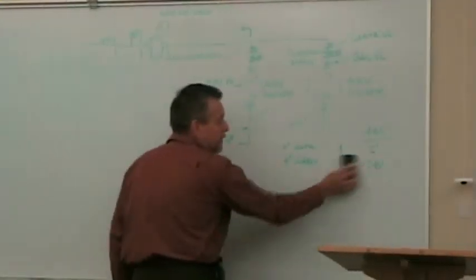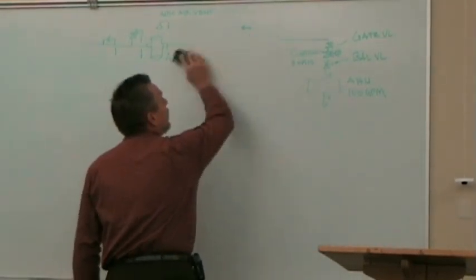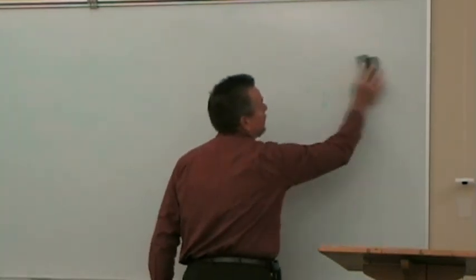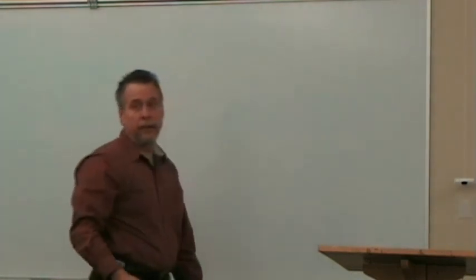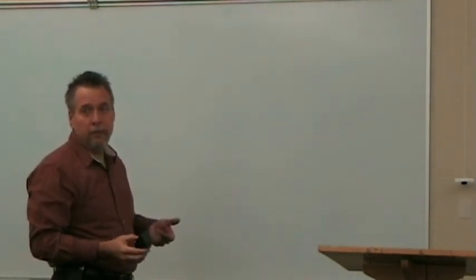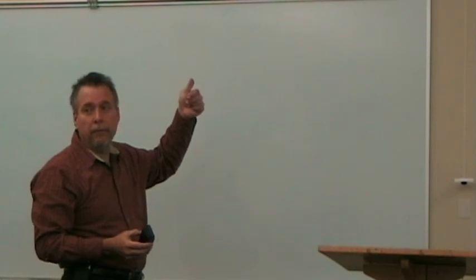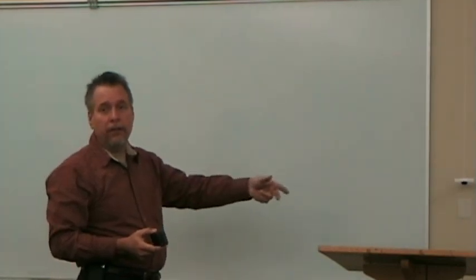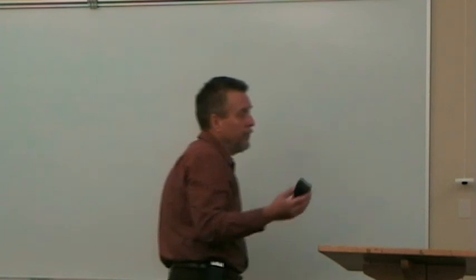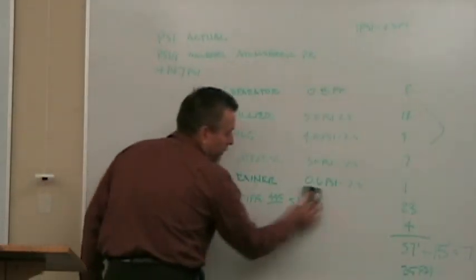But we selected the closed loop system at something less than 6 feet per 100, and maybe a reasonable pressure drop per 100 feet of pipe. In a cooling tower suction, when we go through this net positive suction head calculation, you'll see you don't want any pressure loss. So that pump suction from the cooling tower may actually be larger than your discharge pipe, because I don't want any pressure loss in that pipe. So you might see an 8-inch suction and a 6-inch discharge on a pump for a cooling tower on occasion. Not very often, but it depends, again, on how far that cooling tower is from the pump.